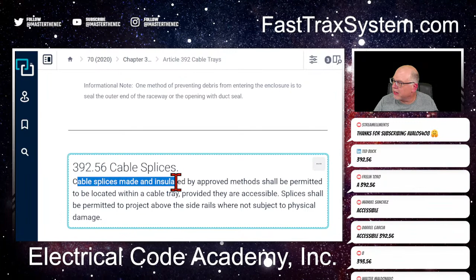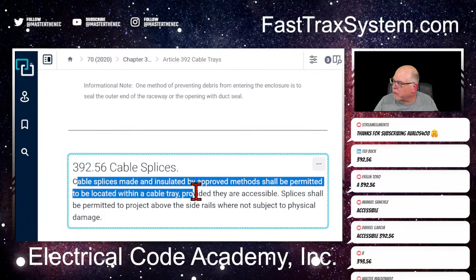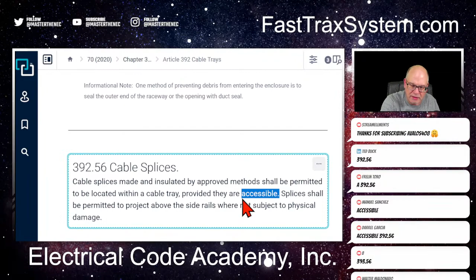Splices, okay. Cable splices made and insulated by approved methods shall be permitted to be located in the cable tray provided they are - and y'all said it and got it right - accessible. So we go back to the question: accessible is the answer, and there's our code reference, 392.56.